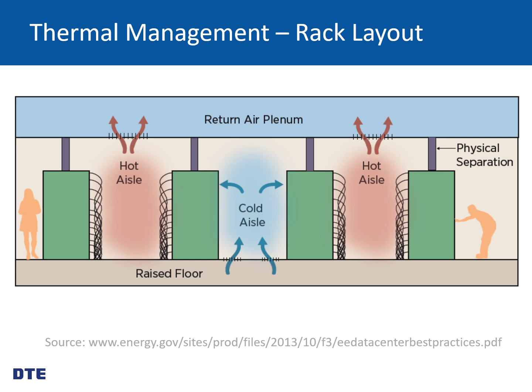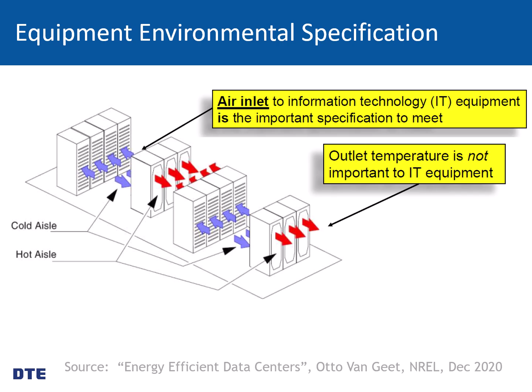But now we're looking at servers - I've seen specifications from suppliers warranting servers to run up to 100 or 120 degrees, allowing the space to go up to 90 or 95 degrees instead of staying at 70-80. That would allow outdoor free cooling with no chillers for more hours of the year, maybe all year. This is being done now, and I contend it's probably the future of the most ultra efficient systems.